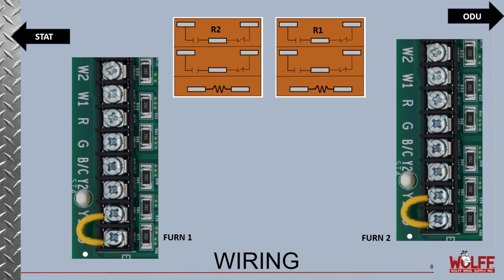So this brings us to our low voltage wiring. In this example, we're using two-stage furnaces with a two-stage outdoor unit. So you always need to isolate the heating circuit between furnace 1 and furnace 2 using relays. Since it is two-stage, we need two relays. If you have single-stage furnaces and a single-stage outdoor unit, just disregard relay 2, W2, and Y2.